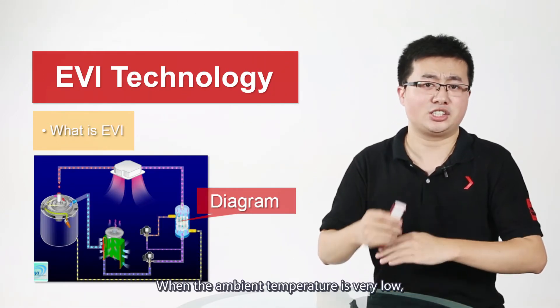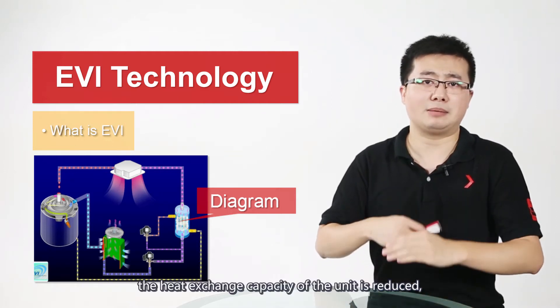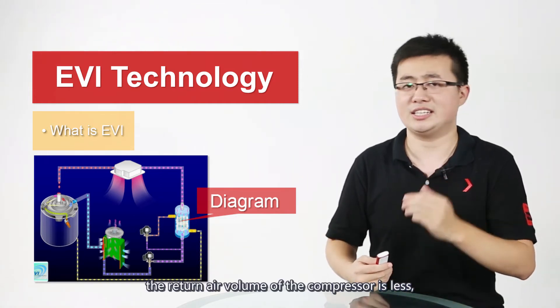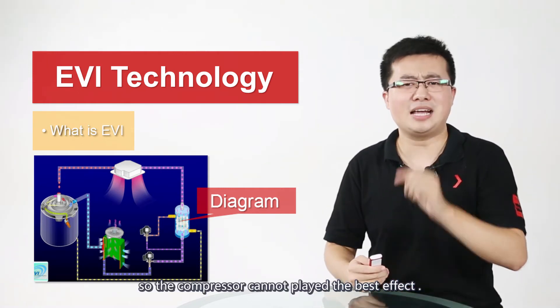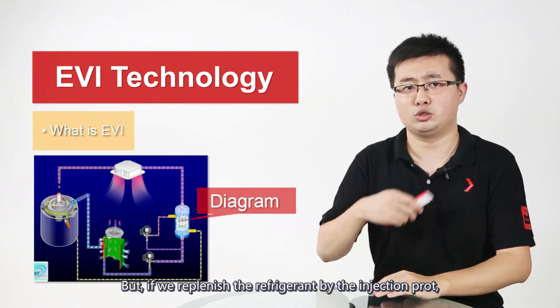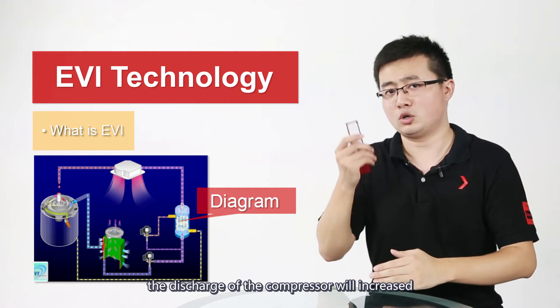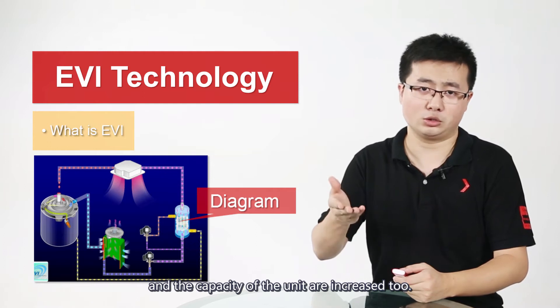When the ambient temperature is very low, the heat exchange capacity of the unit is reduced. The return air volume of the compressor is less, so the compressor cannot play its best effect. But if we replenish the refrigerant by the injection port, the discharge of the compressor will be increased, and so the capacity of the unit will be increased too.